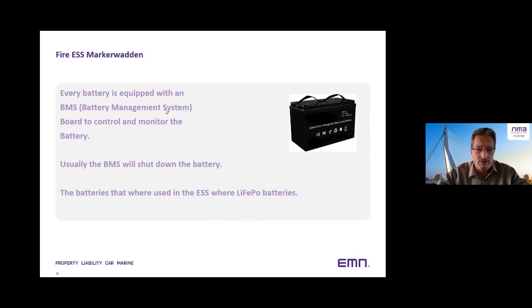What we did find was that it was an electrical cause. Because every battery system is equipped with a battery management system, we checked it with the manufacturer of the cabinet. The cells you can see on the right here have a battery management system board on top of the battery. Usually the BMS will shut down the battery when there is a failure, or when it receives a command to shut down.